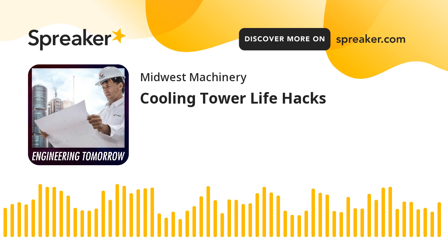Another thing that you'll find is with a gear drive, there's consistently low noise. With the belt drive, it kind of depends on the age and the tightness of the belt. You might start to get some squeaking, some things that are going to be potentially annoying to neighbors or folks around the tower. So those are kind of the big three of gear versus belt drive: the maintenance aspect, the energy transfer through the drive system, and noise.